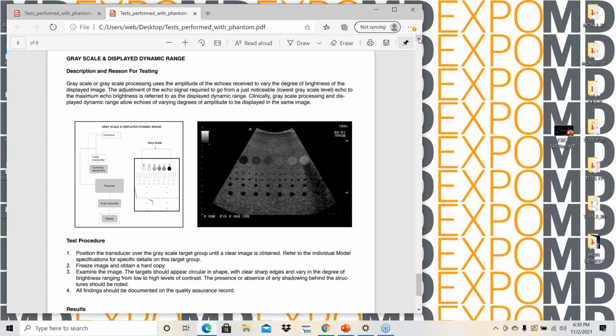So we rotate the Phantom, and now we don't have to penetrate as far to get from the top all the way down. We can just do this. Even if we're only getting 2 or 3 objects, then we slide it 2 or 3 more objects until we get all 6 objects. And the simple explanation on this is you need to see them all. Can you see 6 different objects there? Okay, the 3 to the right, the white ones, if you will, the lighter gray, those are the most dense. The 3 on the left are the least dense, and they go accordingly. The very least dense is the furthest one to the left. And the test is, can you see all 6?